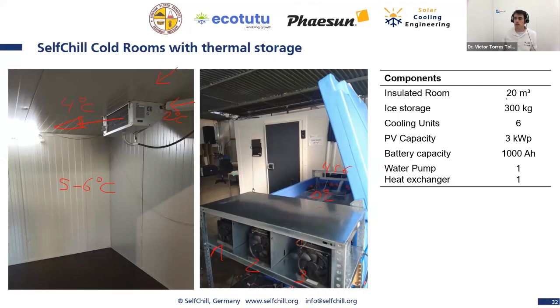So I'm providing here an example for a 20 cubic meters cold room. This has an ice storage of 300 kg ice, 6 cooling units, around 3 kilowatt peak PV panels, and the battery capacity is around 1000 ampere hours. We have a water pump and a heat exchanger that consume both in total around 40 watts of electricity.